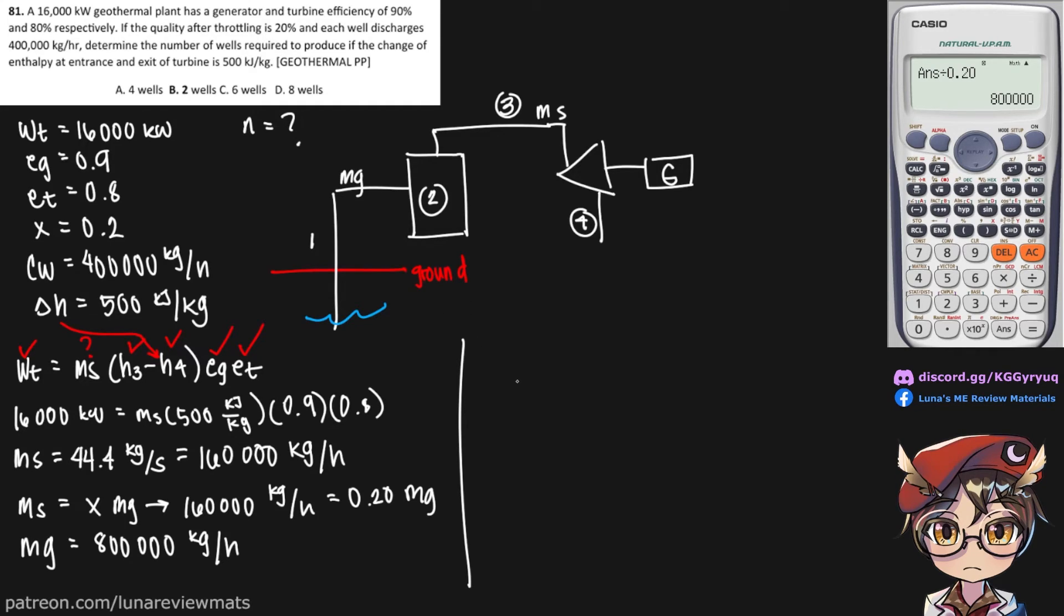So next, to determine our number of wells, n is simply equal to mg over the capacity of our well. And we already have both of these right here and right here. So we just need to put our values in. These are the same units, so they cancel out, and we end up needing two wells to produce 16,000 kilowatts of power for this power plant.